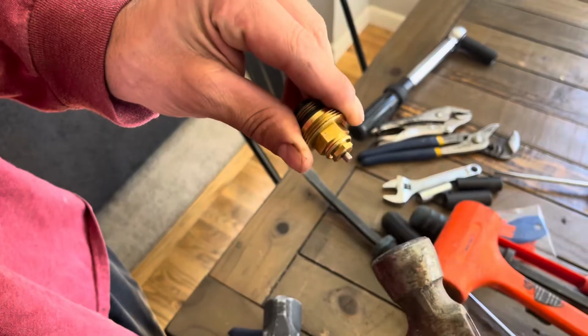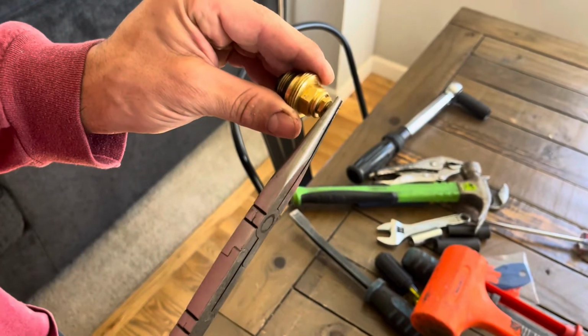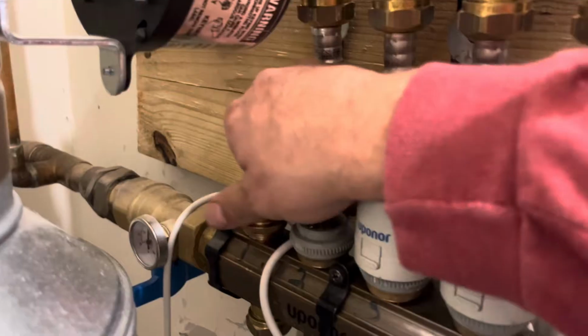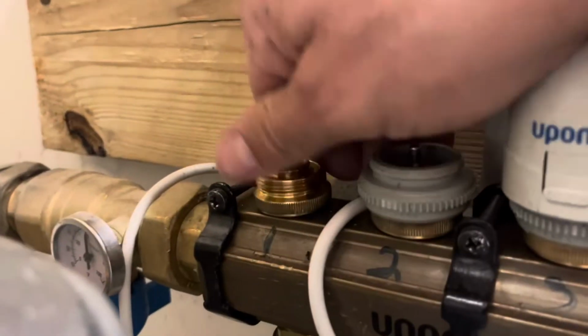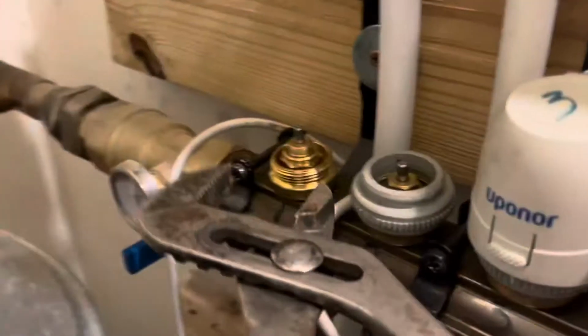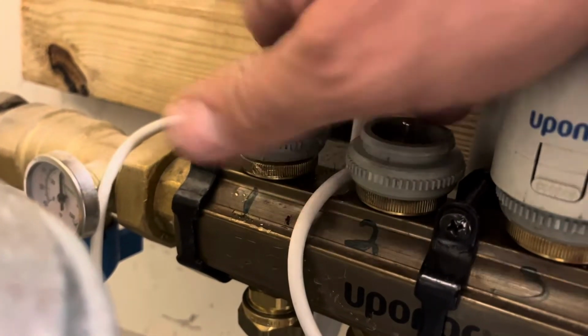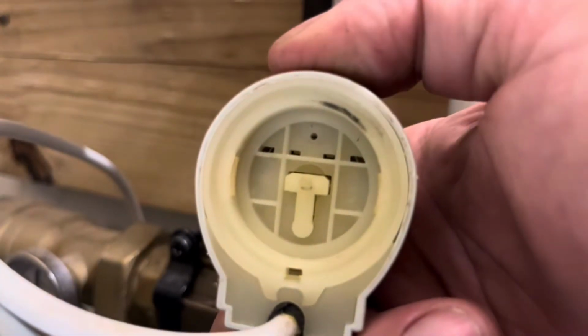So tighten it down, and here's the old one. I tried using needle nose pliers to free it up, but this old one was completely seized. Now I tried doing this while it was in the manifold. You got to be careful though, not to make a bigger accident. So we tighten this ring down, this kind of security ring to hold that pin valve in place. I just used my channel locks and I secured that down. Then I could apply the adapter piece. You just want to make sure you're tightening everything down appropriately.